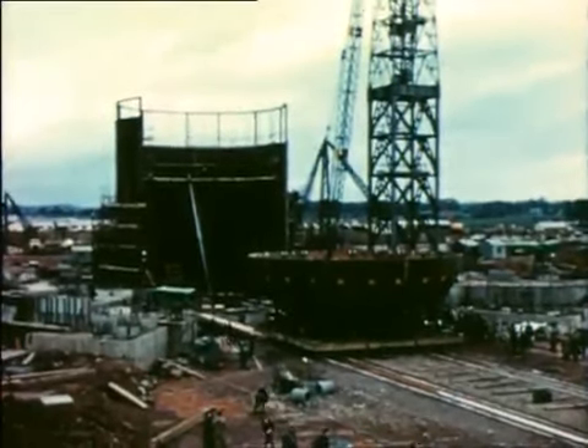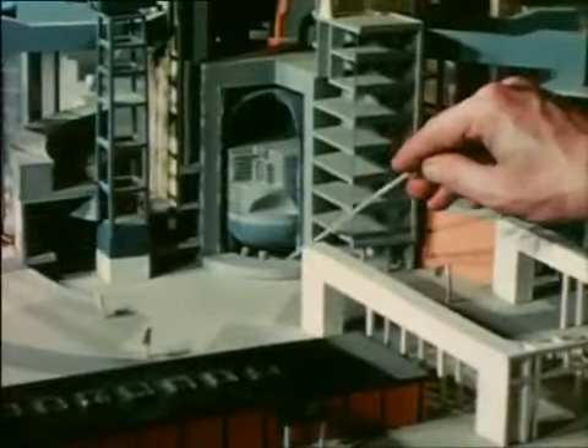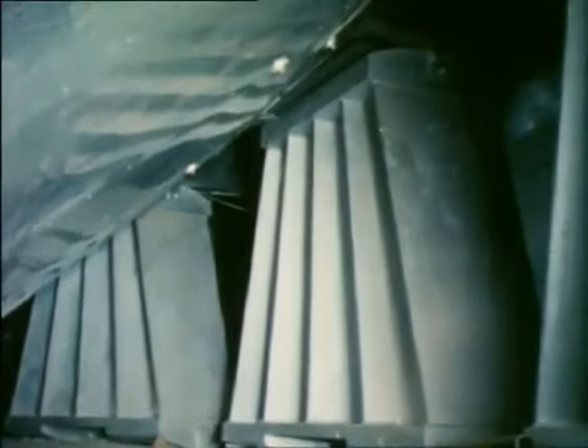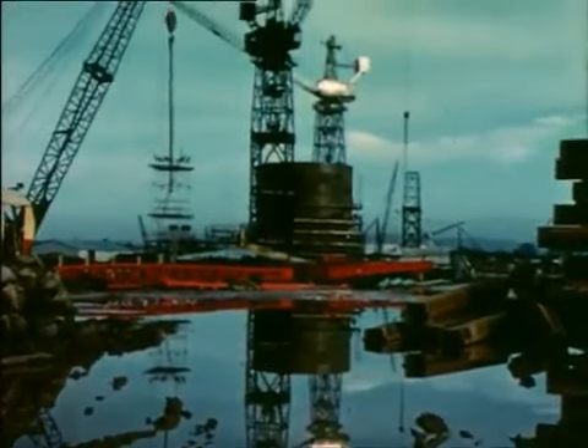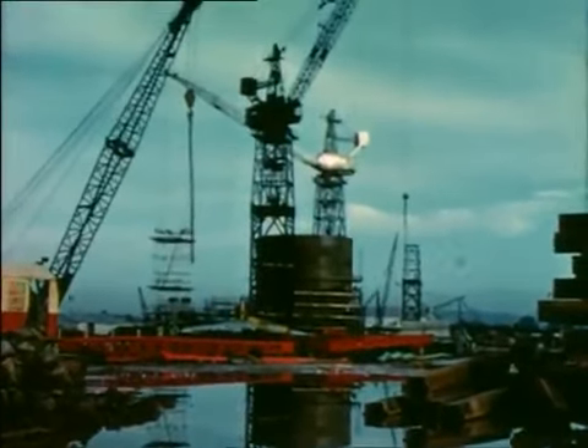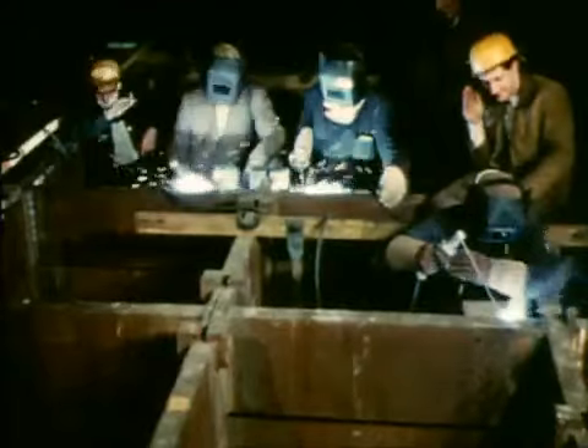The dome is supported on its plinth by specially designed A-frames to take up thermal movement, 18 in all. With the lower dome in position, the gap in the thermal shield was now closed. Here, below the dome, the 8 gas inlets are being welded in position. Above the dome, at the base of the pressure vessel, the diagrid structure which supports the graphite core is being installed.